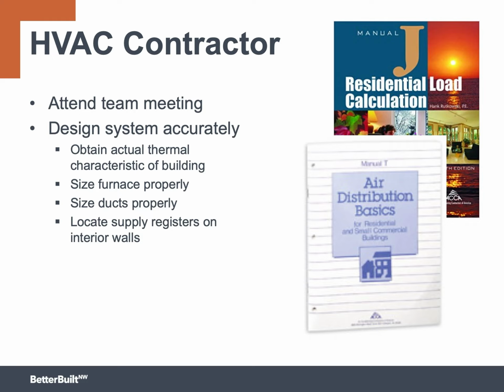Also, think about the opportunities to pull the supply registers back away from the perimeter of the building. Again, in these tight, well-insulated homes with fewer drafts, it's not necessary to push those registers all the way out to the perimeter in order to maintain comfort. So at least entertain the idea that you can avoid the extra material and labor that's required to get those registers all the way to the exterior walls.